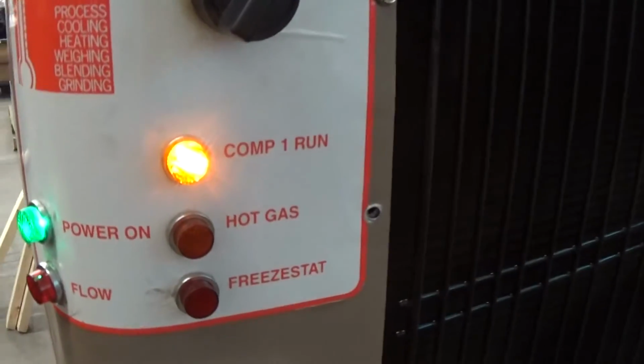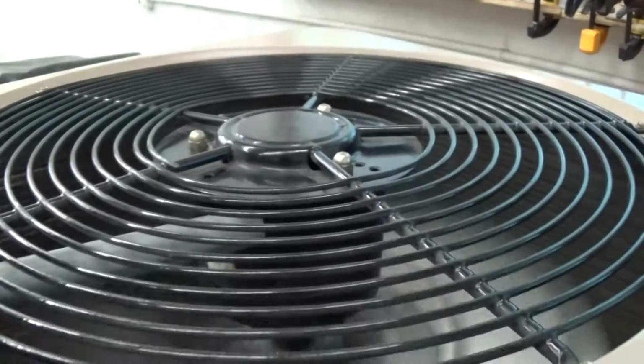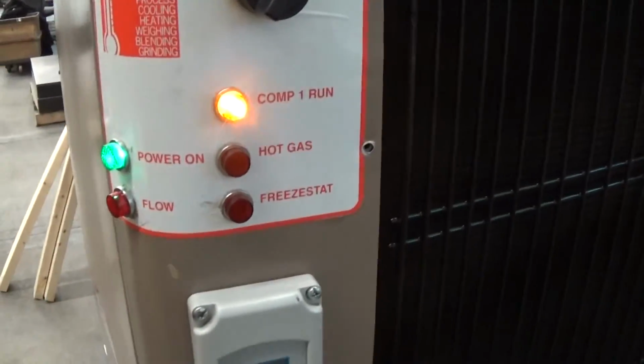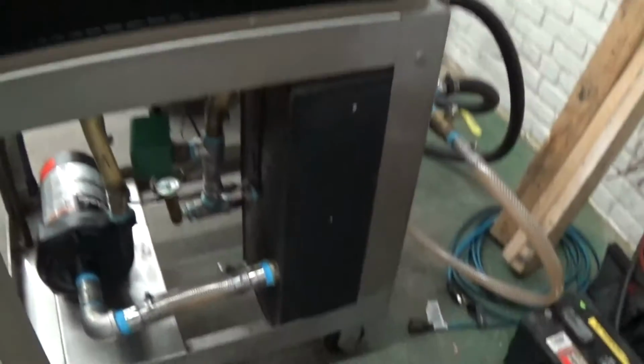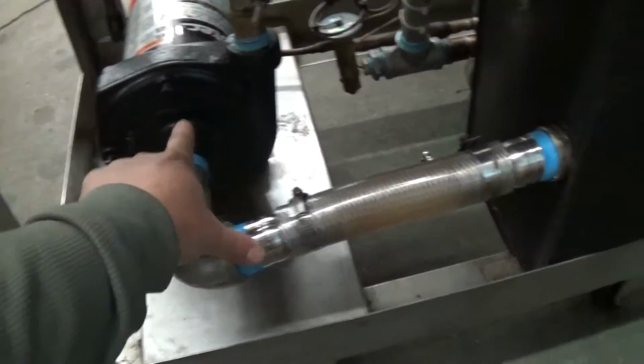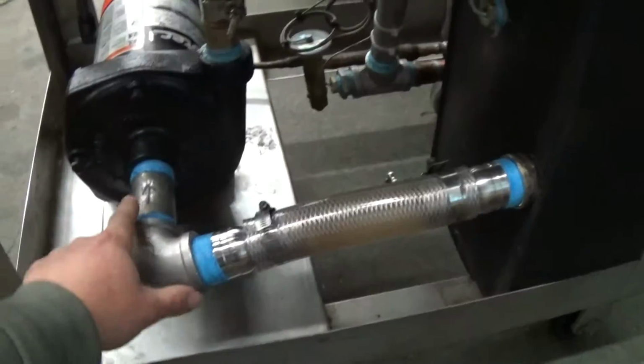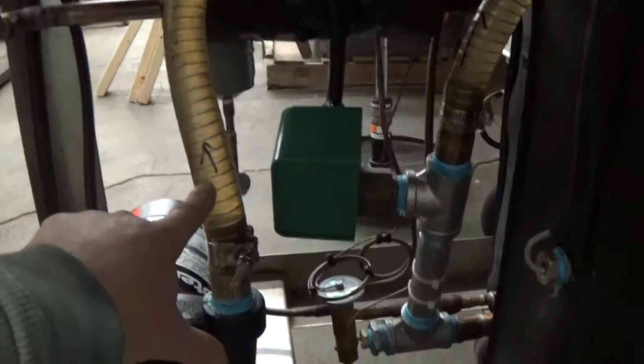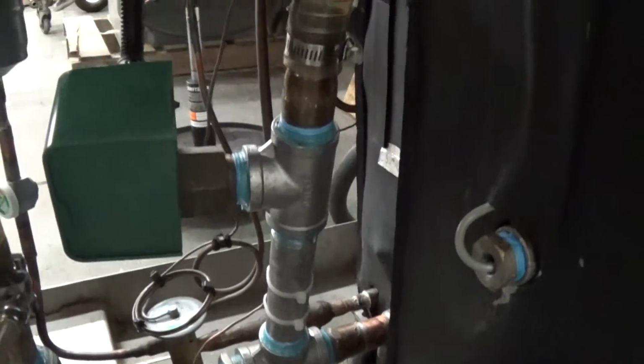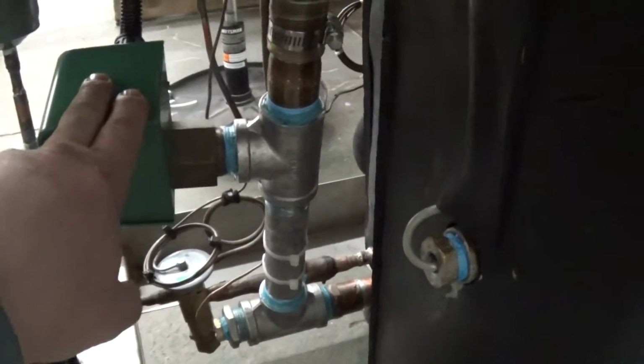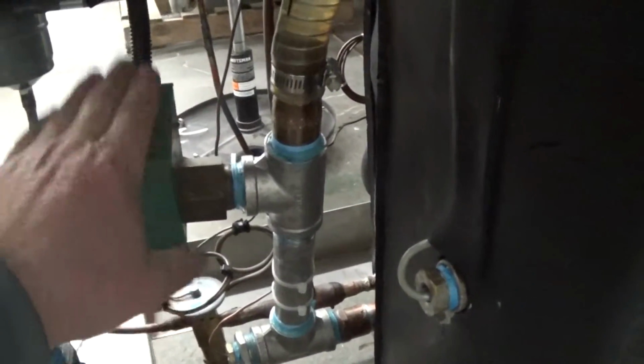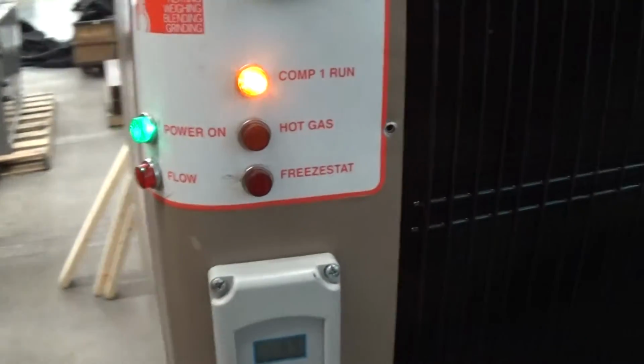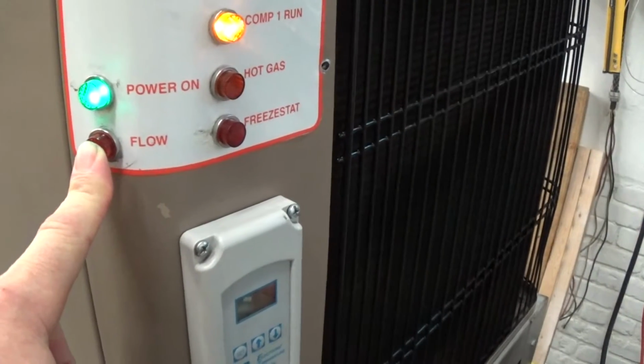The indicator light comes on for compressor 1 run, and our fan is running. And we're going to start to chill the fluid that's in our insulated reservoir right here. The way this works is this brand new pump suctions off the insulated tank, and then I put an arrow here, and then it comes up into the top of the brazed plate heat exchanger, then it comes out here to your process. This here is a flow switch. If you lose flow, and this has some adjustment in it, you'll get this indicator light here saying you don't have enough flow.